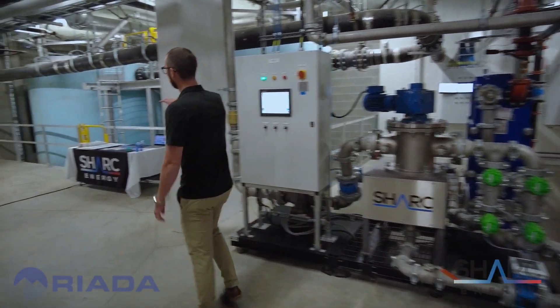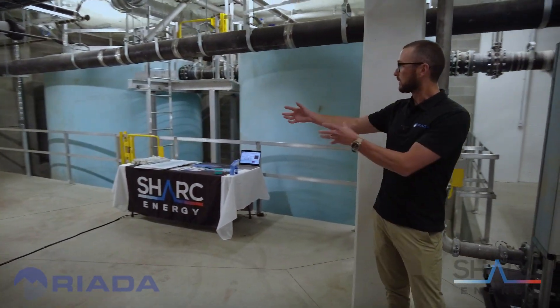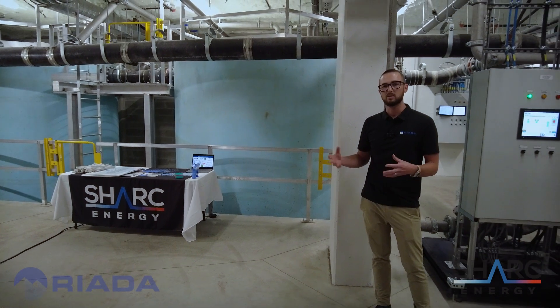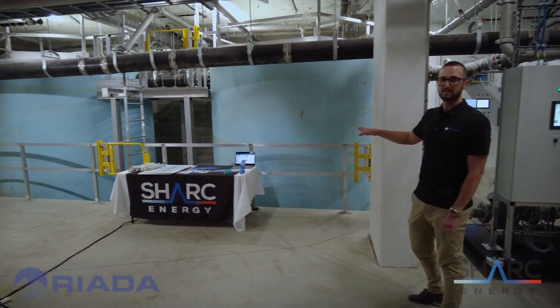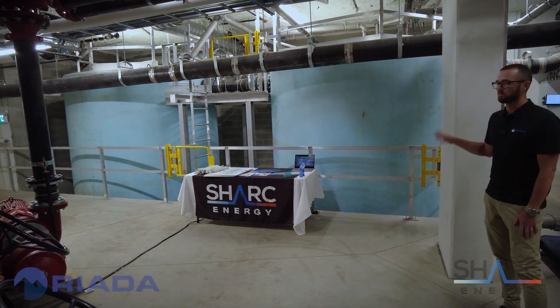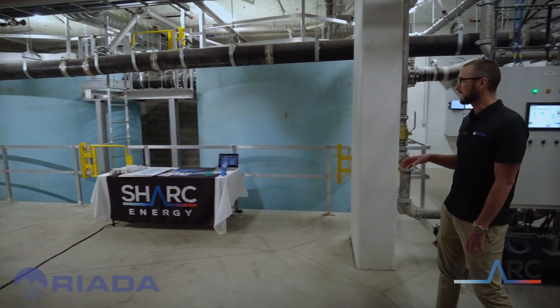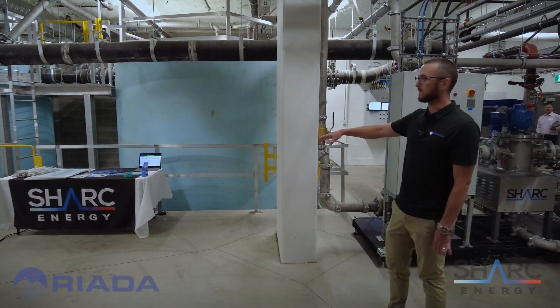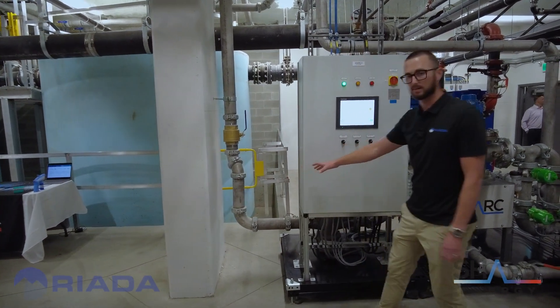Over here on my right we've got two wastewater storage tanks. We're capturing wastewater temporarily to use as a thermal battery in these tanks. Inside the tanks there are submersible solid handling pumps, which will come on as needed and pump raw wastewater through to the SHARC skid.